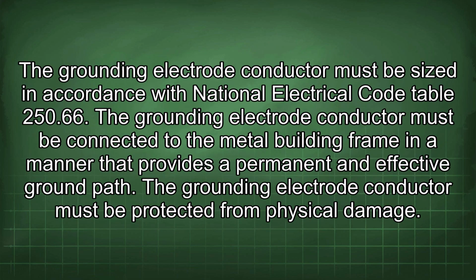The grounding electrode conductor must be sized in accordance with National Electrical Code Table 250.66. The grounding electrode conductor must be connected to the metal building frame in a manner that provides a permanent and effective ground path. The grounding electrode conductor must be protected from physical damage.